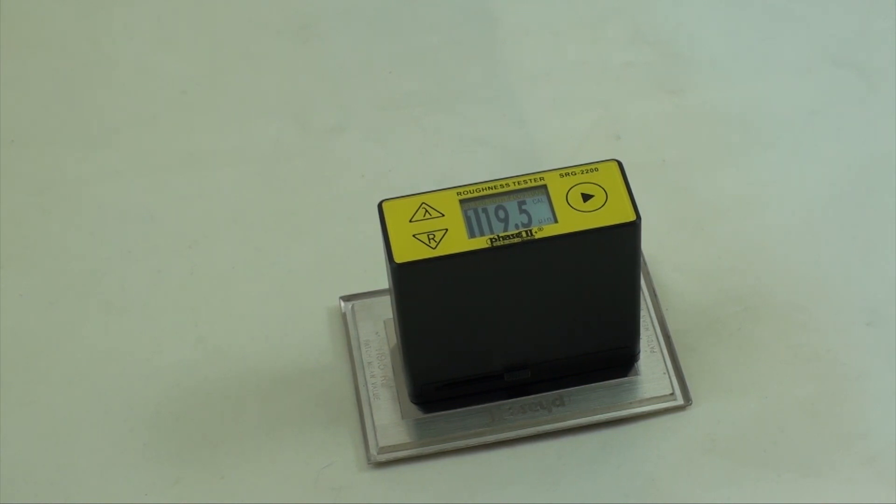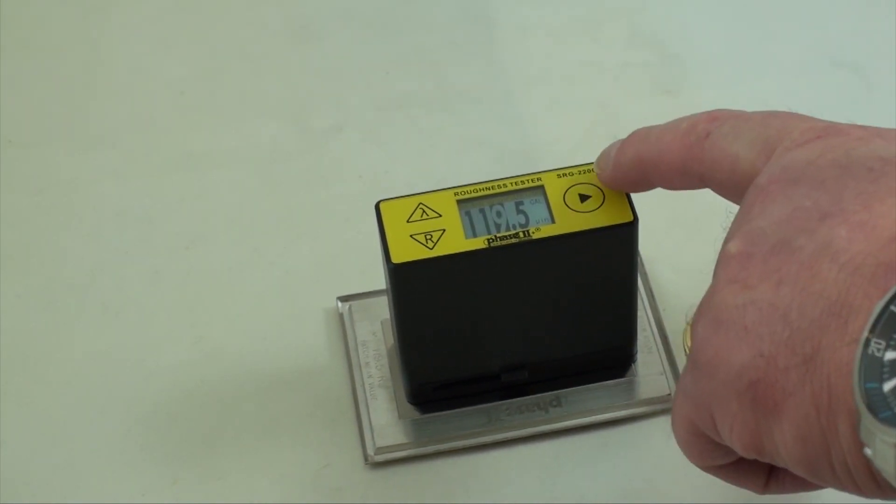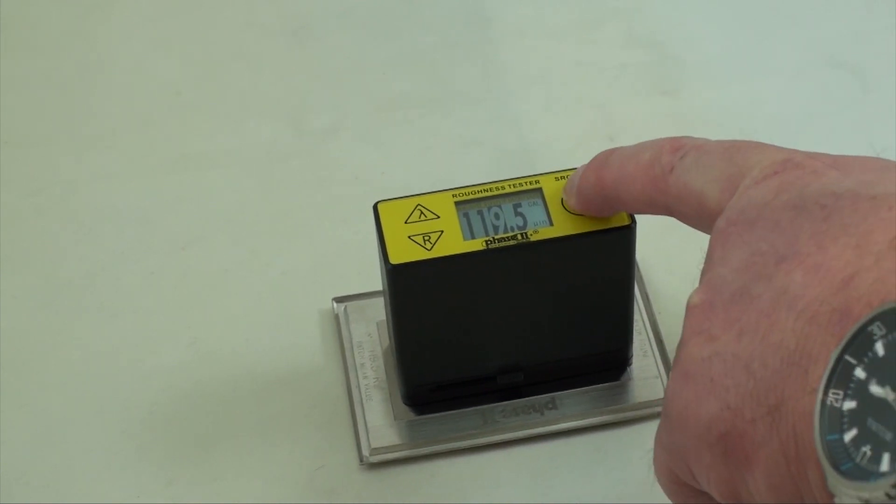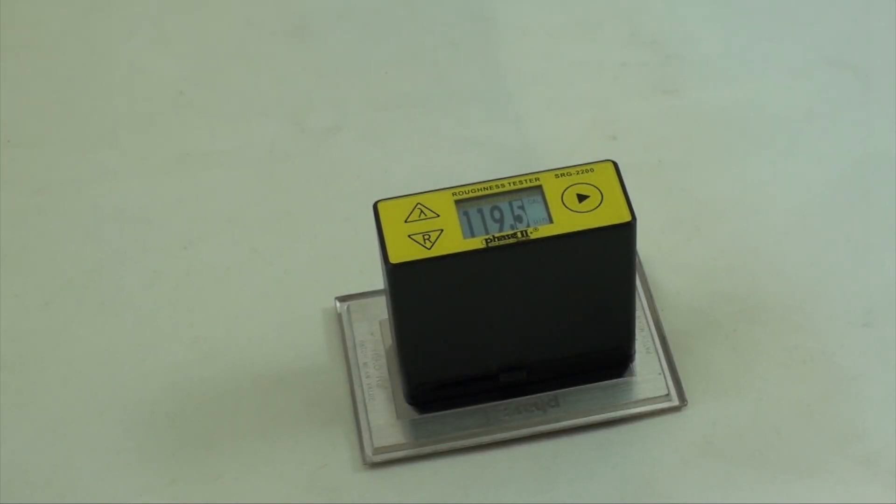Press the right arrow button to toggle to the column to be changed and use the up and down arrow buttons to make changes directly. Once the correct value is entered, press and hold the R button for at least four seconds to save the calibration.